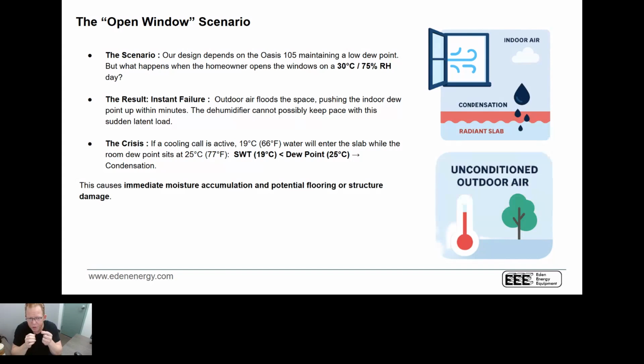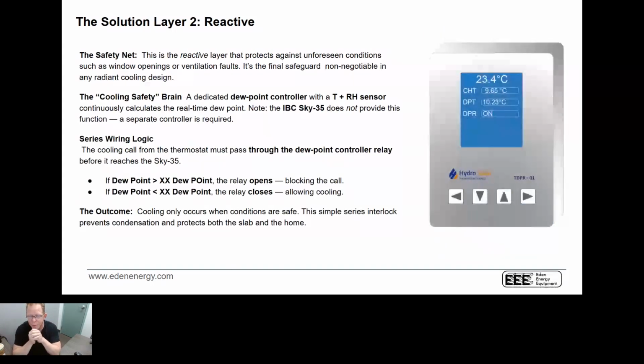So in that particular case, we got to make sure that we have some sort of fallback plan. And the fallback plan is you need to be monitoring temperature and relative humidity and having a dew point controller. So earlier where I talked about the Sky 35 control that I use in my house, it's great for heating, cooling, domestic hot water, but it's not going to take care of humidity. It's not going to be able to tell you what is the relative humidity in the space. There, what you need is a separate dew point controller.